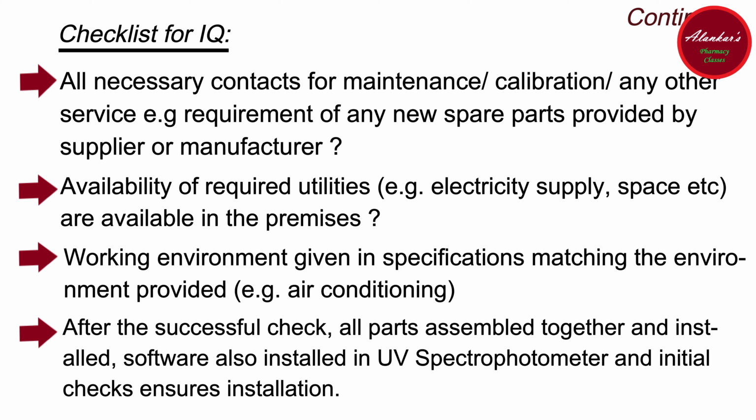After the successful check, all parts are assembled together and installed. Software is also installed in the UV spectrophotometer and initial checks ensure the installation. And after the successful installation of equipment, the documents and procedures should be appropriately kept in a separate file with approval from quality assurance or quality control or any other approving authority.